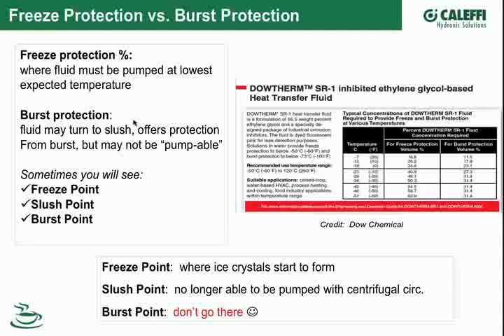Yeah, so it really comes down to freeze protection—that's the temperature at which ice crystals first start to come out of solution. At the end of the day, a little bit of ice isn't going to cause rupture damage to your piping. But as you go colder below that freeze point and more ice crystals form, ice has a lower density than liquid water, so you get expansion, and that creates the pressure that causes rupturing.